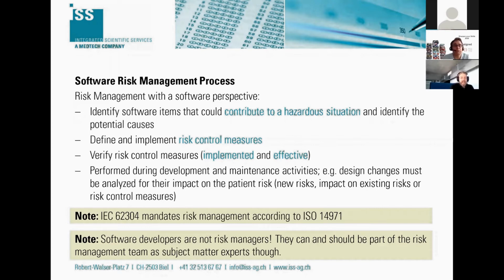The 62304 adds some software-specific perspectives and tells us where exactly to do what. So most of the things are the same, except that for software changes, we need to analyze the impact on the patient risk, if there's a new risk, if an existing risk control measure is affected, and so on.